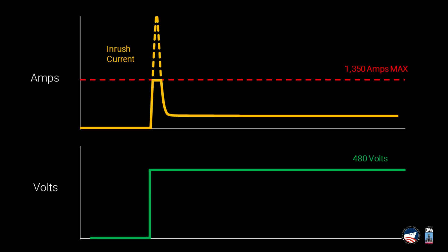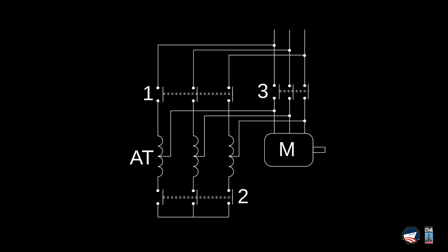The problem with a large motor like that, and something very common in industry, is that the startup load or the inrush current is very, very high. So you could have, as I was taught, five to seven times the actual full load amperage, or FLA, on the motor just from startup. And there's a number of ways to deal with that, and in fact, it's very common in industry.